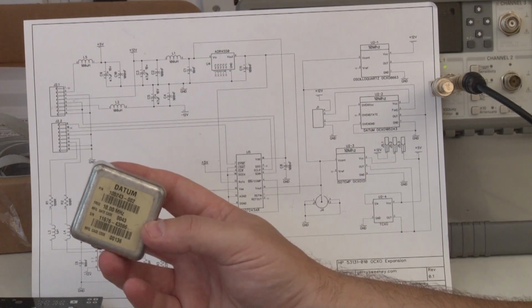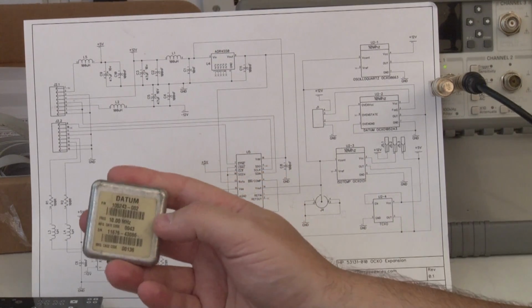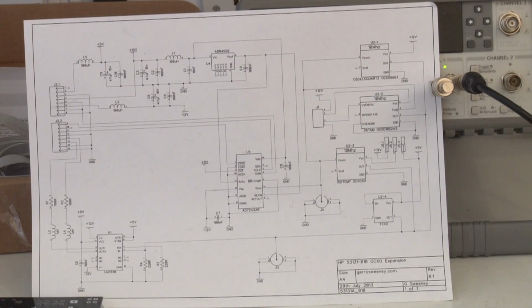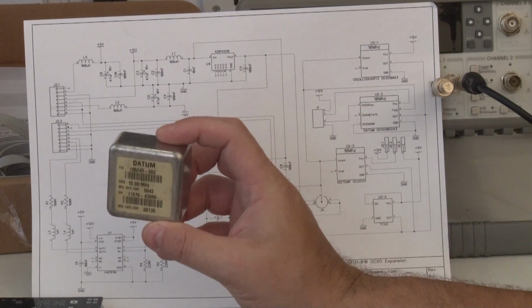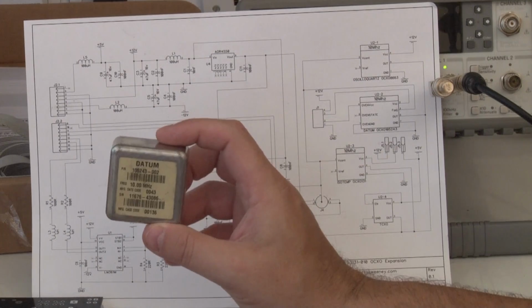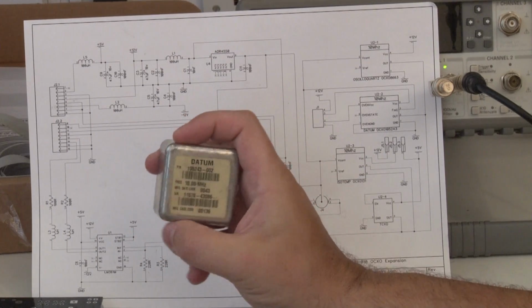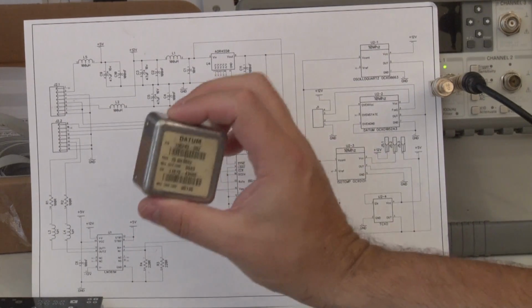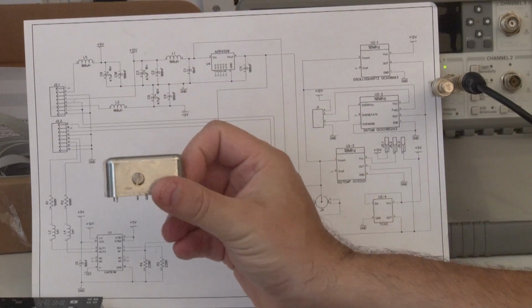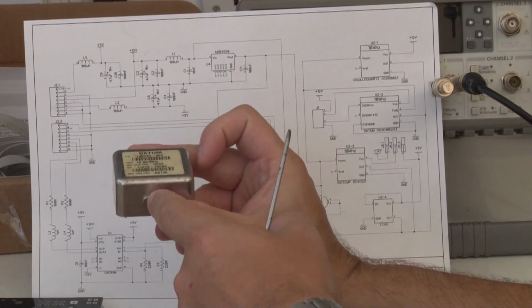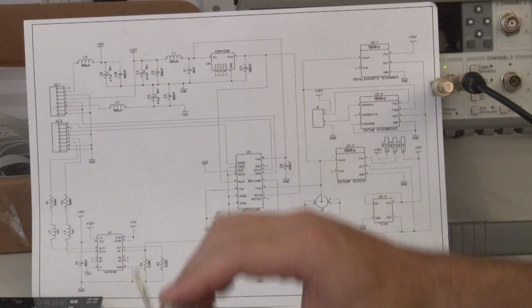And in fact, the OCXO I'm going to use, which is made by - which one is it - a Silquartz part, has voltage control that trims it to plus or minus 0.3 parts per million. So it's a very narrow window, but it's there to allow you to trim and tune the voltage. This one, for example, if I open it, has a trimmer inside, so you can actually trim these off. They all have different variations, but the basic structure is the same.